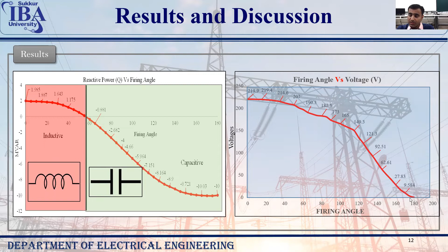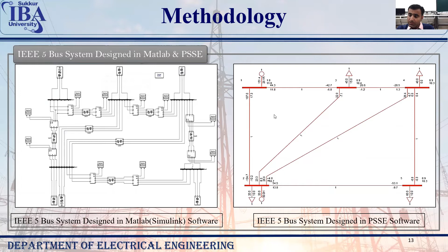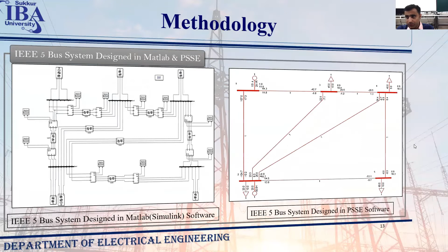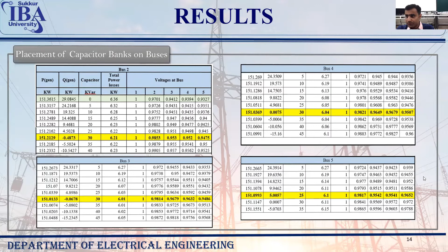After that, we designed the system in MATLAB as well as PSSE. The main purpose of designing it in PSSE is for the sake of the PSO algorithm. When we add a capacitor bank, it is much easier than in MATLAB. After designing it in PSSE, we add a capacitor bank on each bus, and we have taken the value of power generation, total reactive power generation, the value of capacitor that is installed at each bus, and the total power losses, and this is the voltage at each bus.